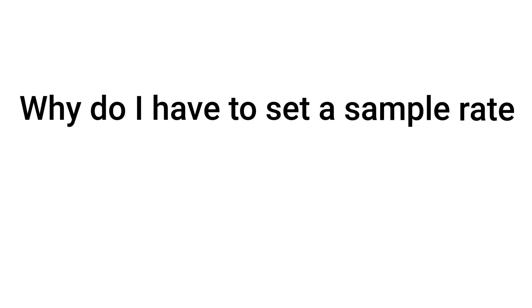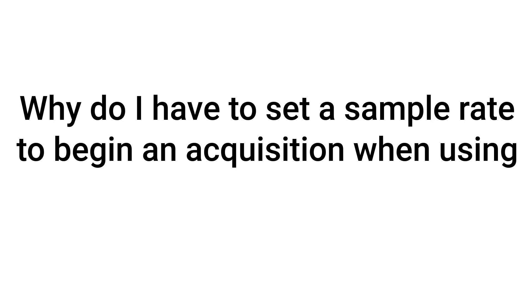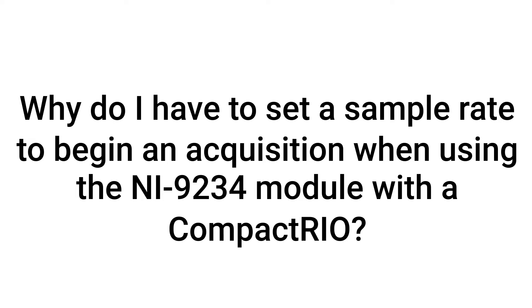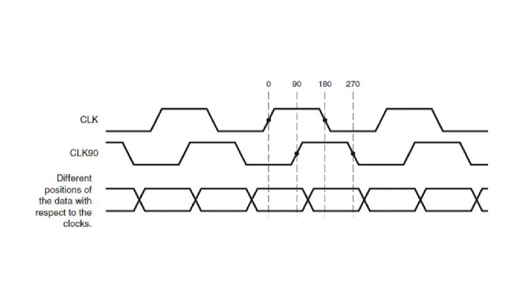Why do I have to set a sample rate to begin an acquisition when using the NI9234 module with a CompactRIO? The NI9234 is a dynamic signal acquisition module which utilizes delta-sigma converters and an oversample clock. The NI9234 must use the anticipated sample rate to configure the oversample clock.